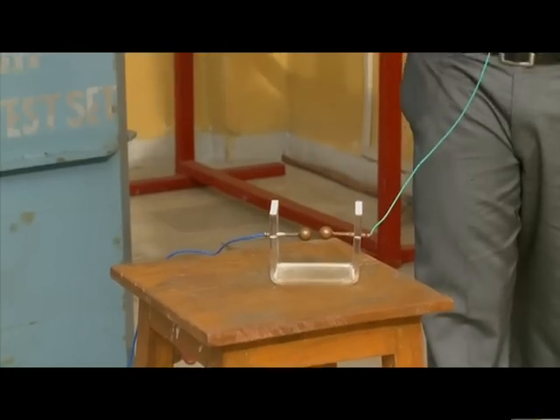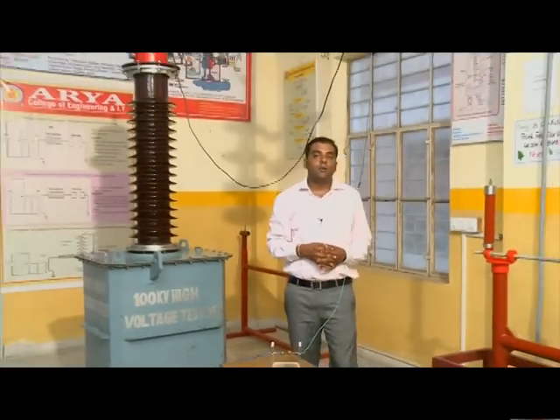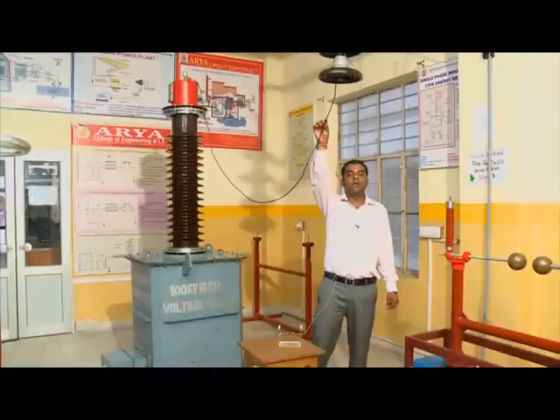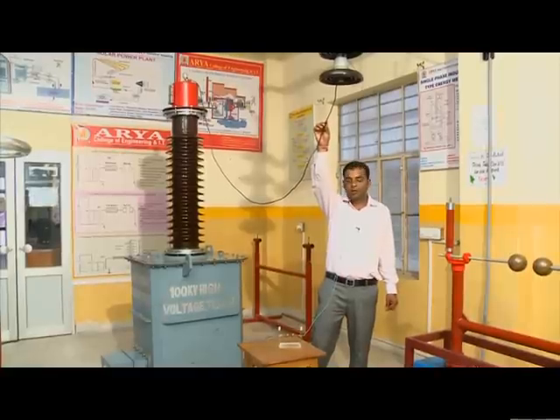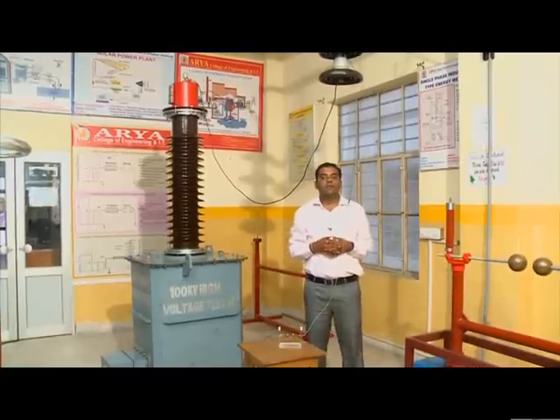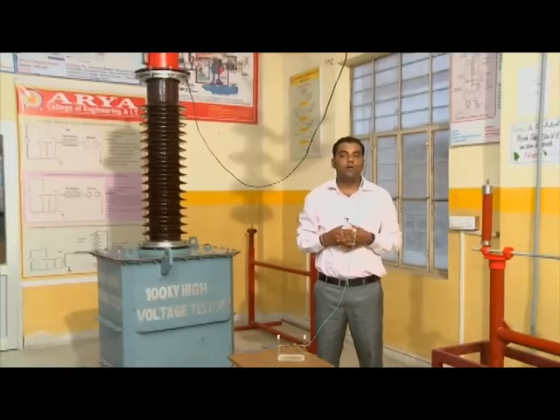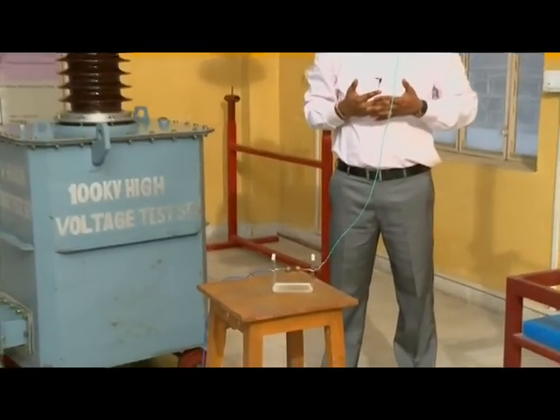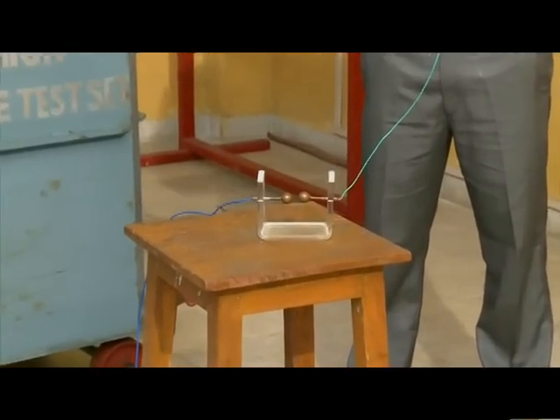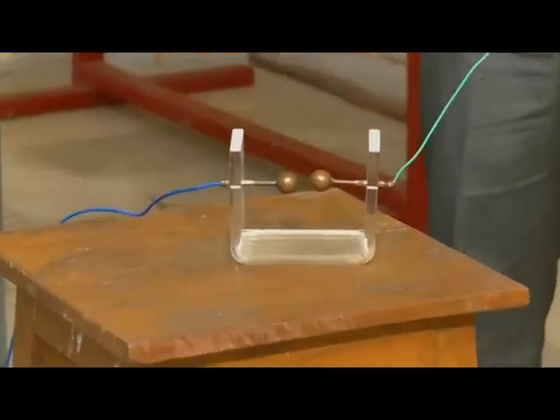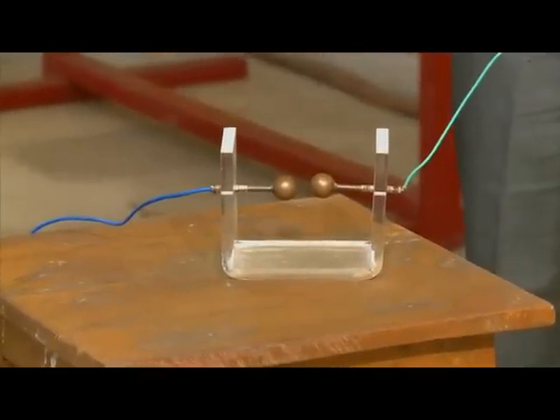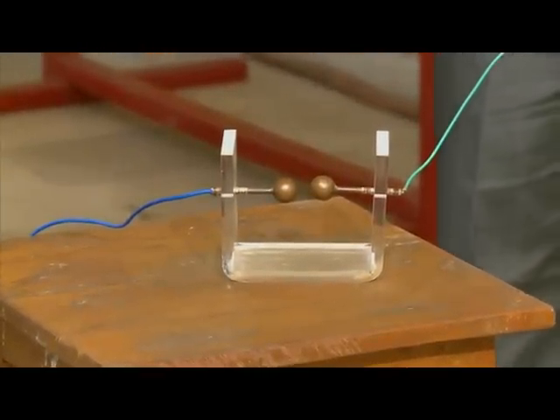Now we apply the input voltage to the individual unit of the insulator string, and after some time the breakdown of air will occur. That value of voltage at which the breakdown of air occurs is called the spark over voltage of the individual unit.